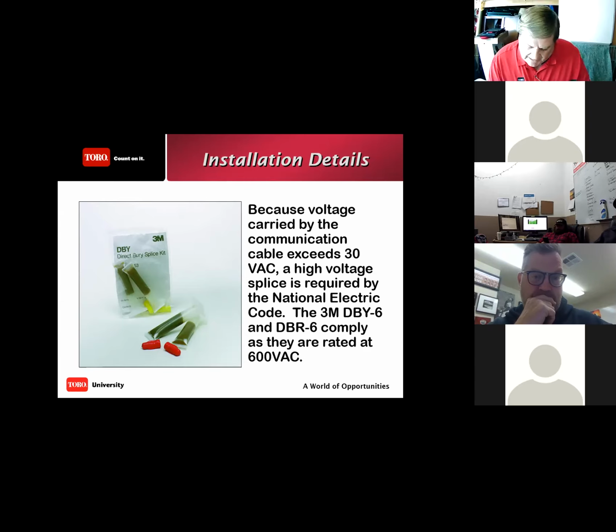One, because on many systems, that 2-wire path is live 24/7, 365 days a year, holidays included. That's a lot of energy through that 2-wire path consistently. Looking for flow, looking for moisture information. It's checking on the valves. There's a lot going on in that 2-wire path. And because of the communication piece, that's DC, which means that your potential for corrosion is much greater. So we have to be careful with the wire connection.